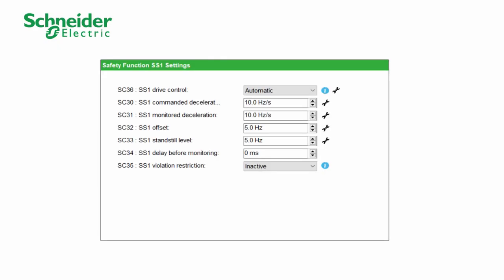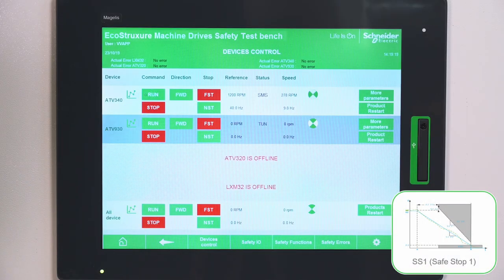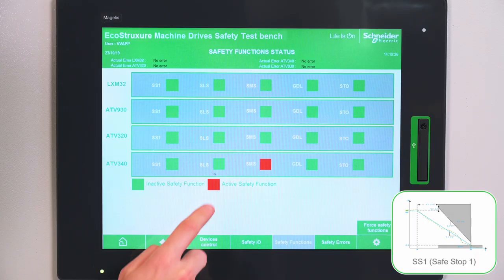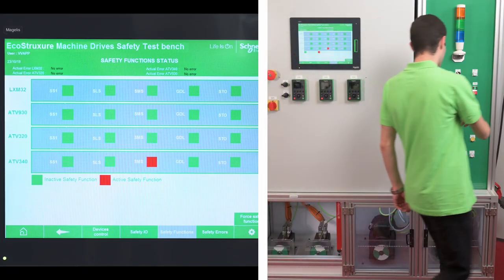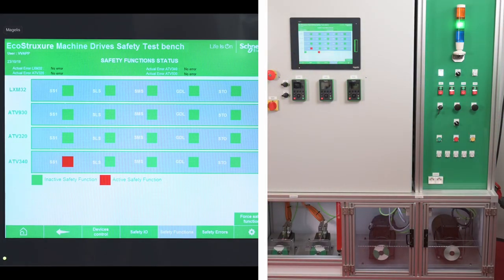We configured SS1 using SoMove software. Now we activate SS1 using an emergency stop. We can see the motor stops in Safe Stop 1 using a safe deceleration ramp. We can also see the activation of the SS1 function in the HMI.